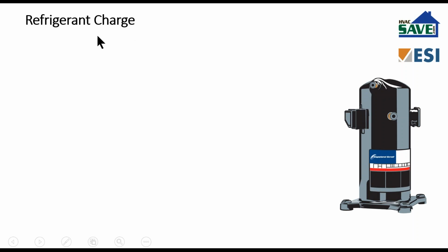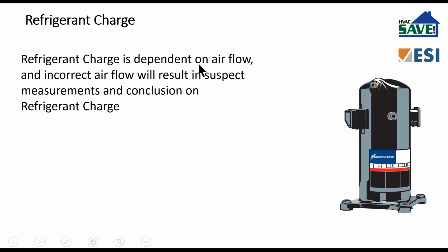Okay, let's touch on the second performance driver, refrigerant charge. Refrigerant charge is dependent on airflow, and incorrect airflow will result in suspect measurements and conclusions on refrigerant charge, okay? In other words, there's a dependency here, and that dependency is highly relevant, highly impactful.